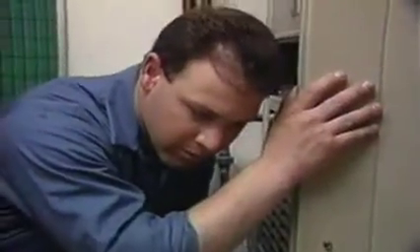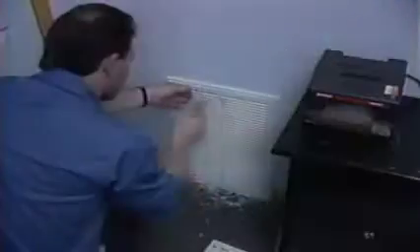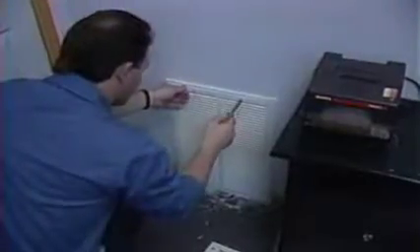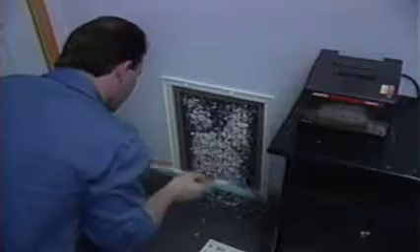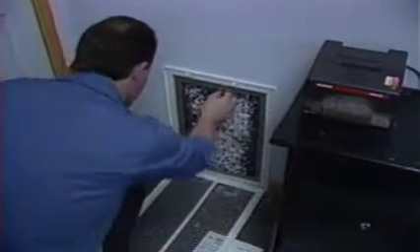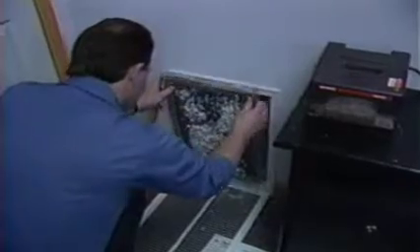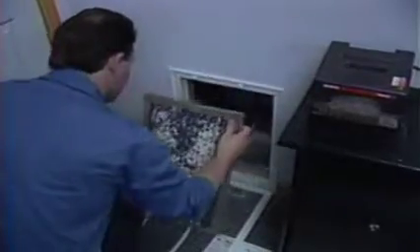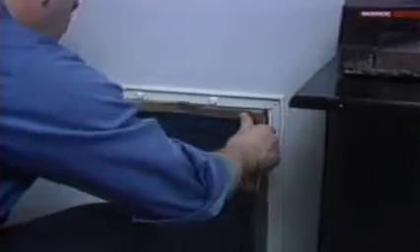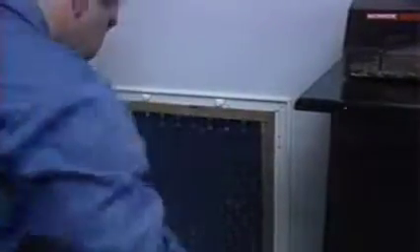The first thing the technician checks is the indoor fan motor. The motor is running, so the air filter is checked and found to be severely restricted. The return air filter is located near a paper shredder, which has created this condition. The filter is replaced, and the technician will recommend that the owner move the paper shredder.